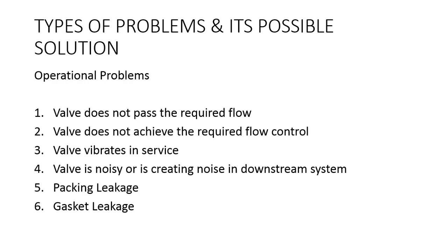A diffuser can be used in the downstream pipe. Pipe configuration: flow turbulence can be there due to piping. Check for appropriate distance to the upstream valve, elbows, tees, etc.